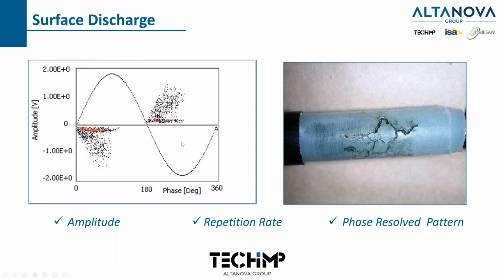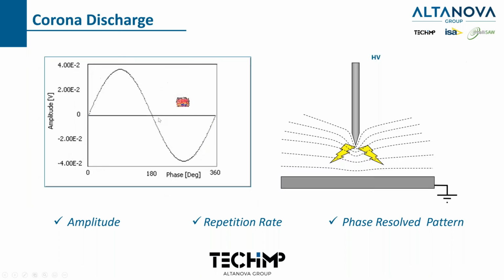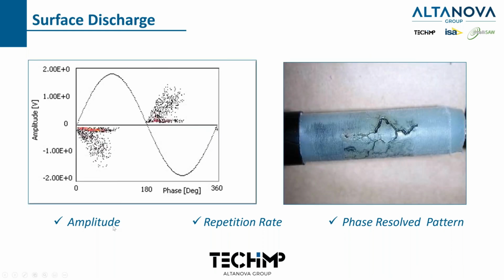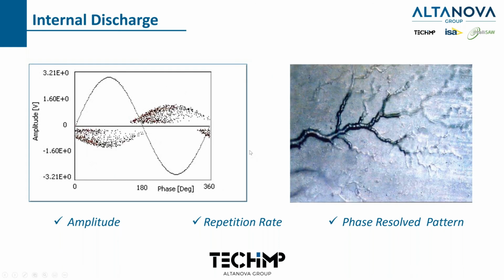Here's the phase resolved pattern for surface discharge. Obviously that looks a lot different than that. And then we'll take a look at amplitude and repetition rate, and then we'll determine if it's dangerous to that splice or bus bar or termination or whatever. And this is the damage that surface PD does to your cable or splice or bus bar. And then finally, the bad boy is internal discharge, of course, for the cable, the most dangerous.